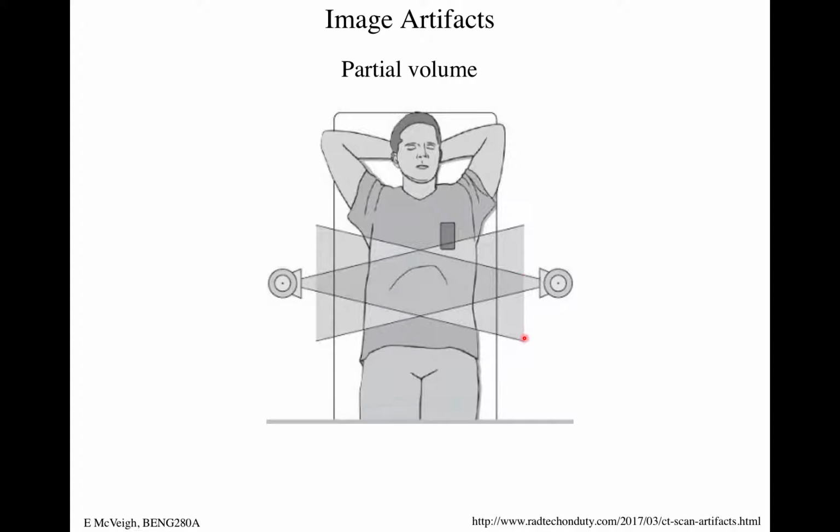The detector is usually designed so that it rotates around the patient, and then this is the Z direction. So the detector I've been showing you in those slides has 256 samples this way. Into the page it has 1,000, right, or 820, but 1,000 that way.